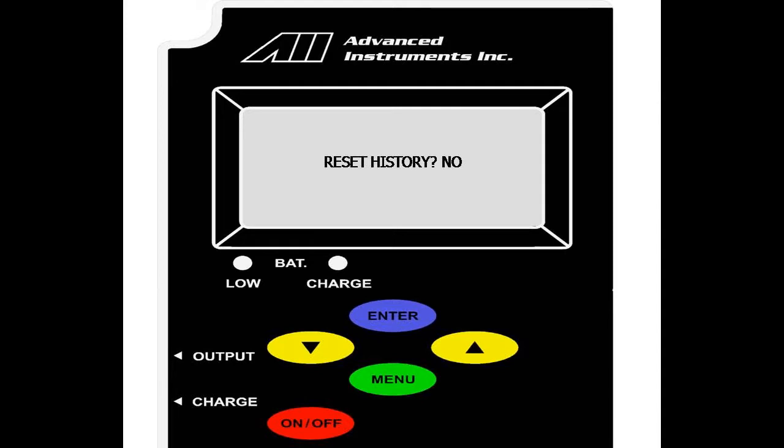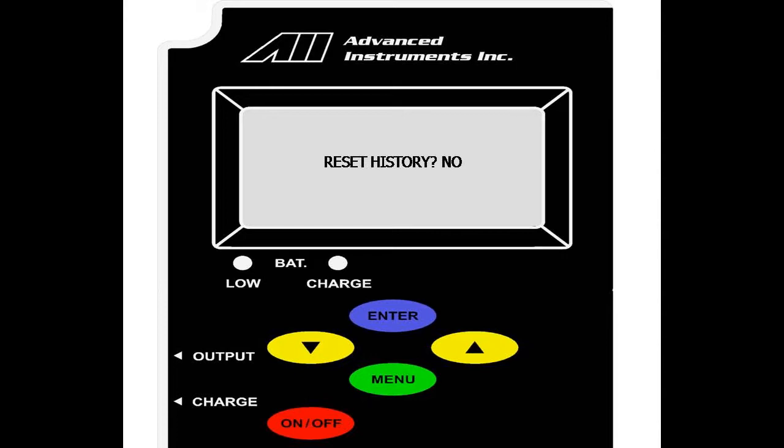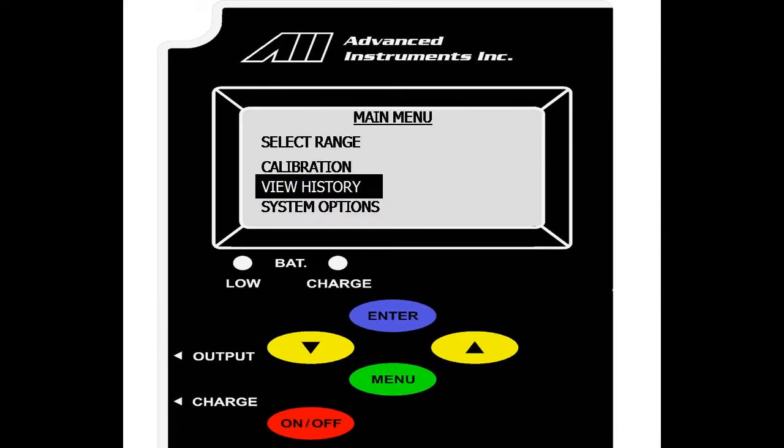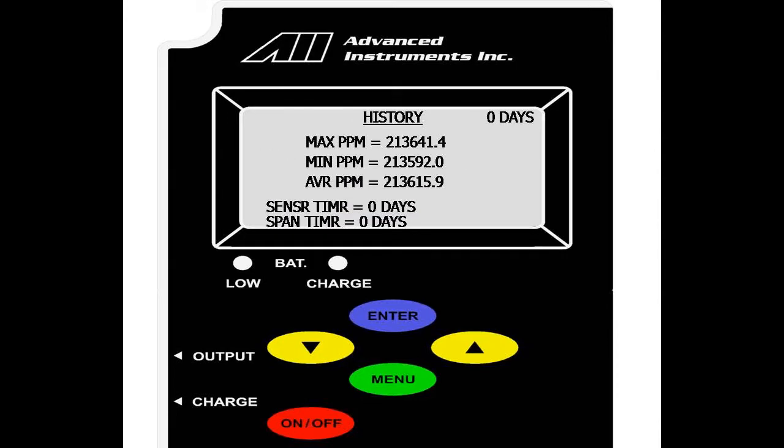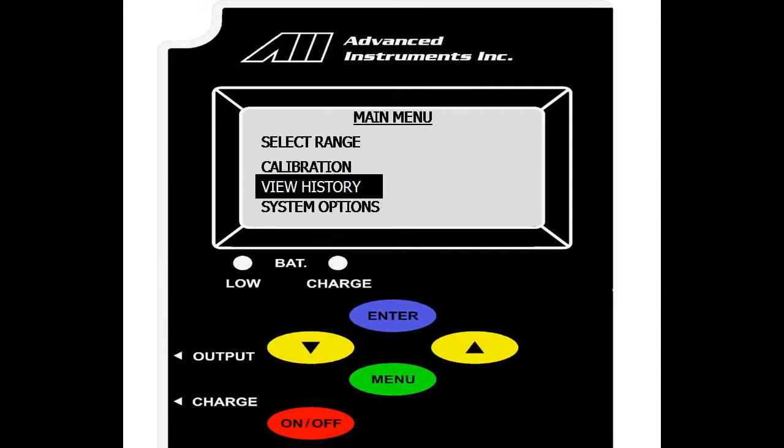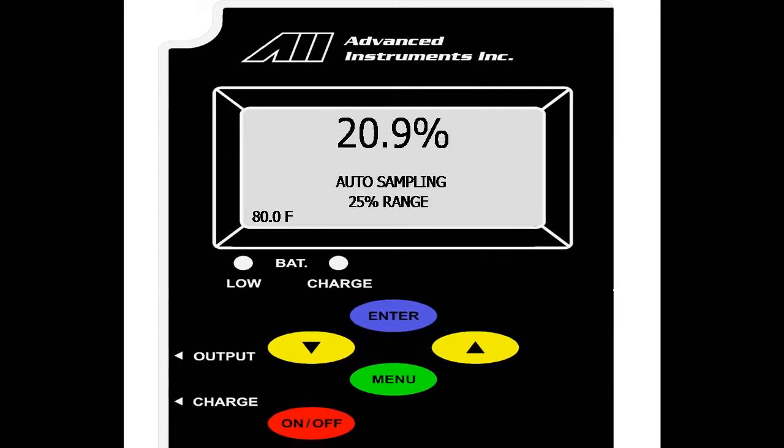Once you hit enter, you are prompted if you want to reset history. You can select yes or no with the up or down buttons. Enter on yes. As you can see, the view history menu was reset and all current values are the current value of the sensor as of now. That was the view history option for the GPR 1200 oxygen analyzer.